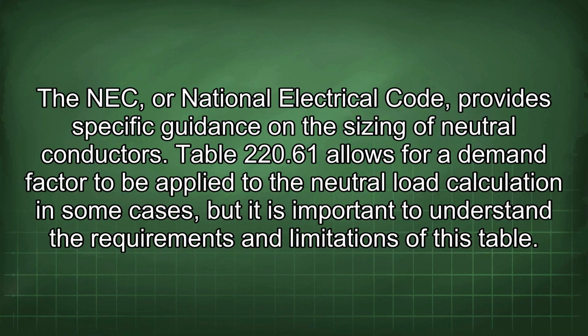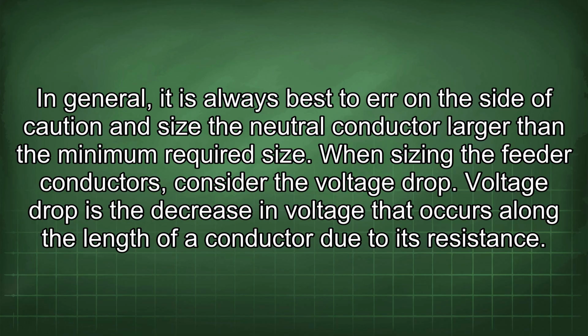The NEC, or National Electrical Code, provides specific guidance on the sizing of neutral conductors. Table 220.61 allows for a demand factor to be applied to the neutral load calculation in some cases, but it is important to understand the requirements and limitations of this table. In general, it is always best to err on the side of caution and size the neutral conductor larger than the minimum required size.